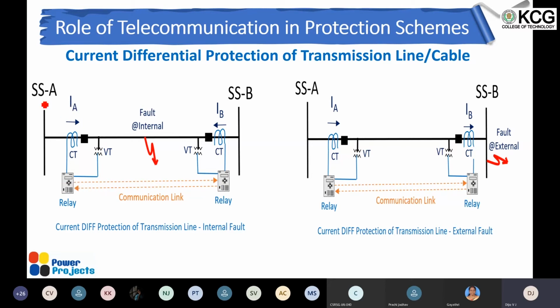Vice versa also, the current measured by the relay at substation A is sent back to the substation B relay, and the calculation will be done independently. If there is a resultant current for a fault here, then this relay is going to give a command to open this breaker, and this relay will give a command to open this breaker. So that's what it does.